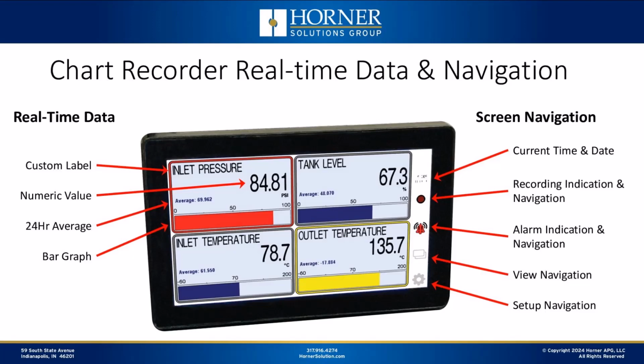And then on the right-hand side, and this applies to just about every screen and not just your numeric data display, it also has icons and other screen navigation and status indicators. So it'll show the current time and date. If you're doing a special recording, if you're running a special test, maybe a 10-minute test or something, it has a recording indicator that will show you through its graphics that a recording is currently going on. It's got an alarm indicator, which is also used as a way of quickly navigating to an alarm screen, so you can see alarm details.